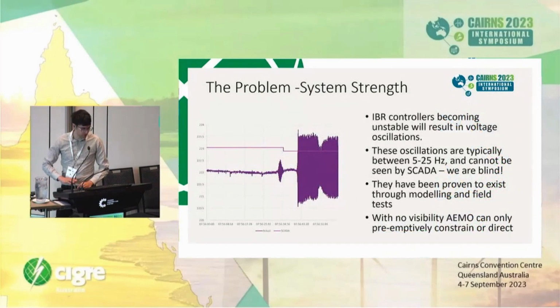Now, why is this a problem? Well, controlling inverter-based resources is a challenge in weak systems, and the way system strength issues manifest is as voltage oscillations. You can see there on the graph, that's an example of an inverter-driven oscillation at about 17 to 18 hertz. And the problem for AEMO is that these kinds of things we're completely blind to. You can see there's a light purple line there. That's what the control room would have seen over their SCADA systems. You can see it's completely hidden the issue. So we're completely blind to these issues. We do not see them just due to the nature of the SCADA systems.